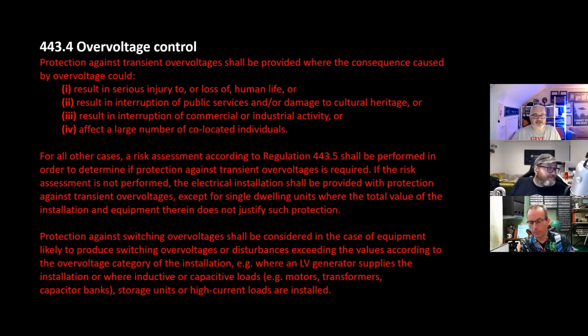For all other cases, a risk assessment according to 443.5 shall be performed in order to determine if protection against transient is required. We now know that risk assessment is very limited in why you would actually do it in the first place. If the risk assessment is not performed, the electrical installation shall be provided with protection against transient overvoltage, except for single dwelling units where the total value of the installation equipment does not justify it. We also know there is an IEC version of that, which pretty much once you do that, it's going in anyway. So this is the existing reg: protection against switching shall be considered in case of equipment likely to produce switching overvoltages.